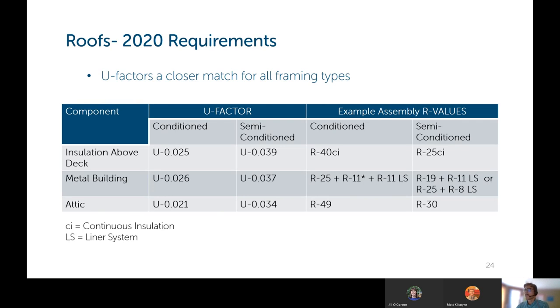So starting with the roofs, what was changed here is the U factors for the different framing types. Metal, attic, and insulation above deck are all a closer match now. And again, there are categories for a conditioned space, which is just typical buildings that are heated and cooled to human comfort. And then you've got semi-conditioned, which must meet those requirements that I mentioned earlier for low heating and cooling loads. And to the right here, we've got examples of what R values would meet those requirements for the different insulation values. And the semi-conditioned spaces are all less than the conditioned spaces.